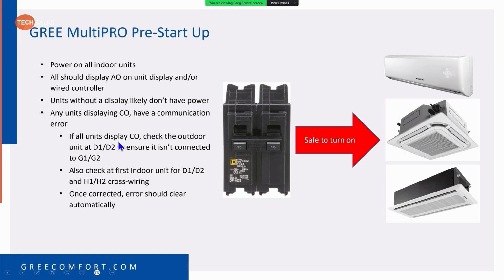If all units display CO, check the outdoor unit at D1 and D2 to ensure it isn't connected to G1 and G2, because that could give you the error code. Also check that the first indoor unit, the D1 and D2, make sure we didn't get the wiring crossed up to H1 and H2. Some of you guys are probably thinking, why would you do that? Trust me, I've had that phone call. So just double check your wiring. Once it's all corrected, the error code should clear automatically.